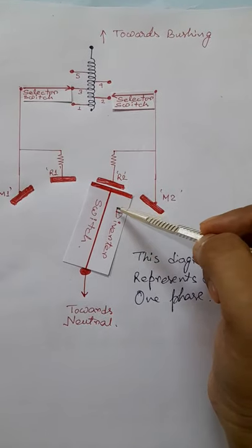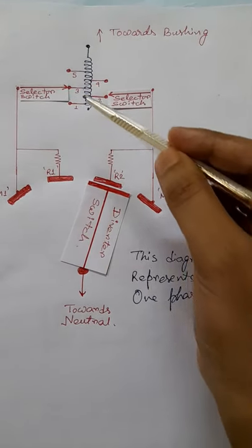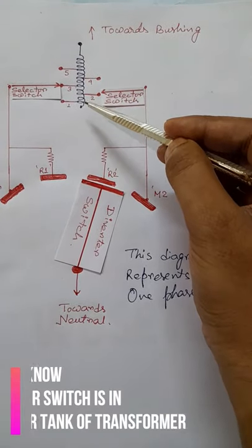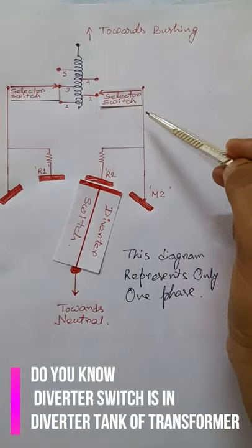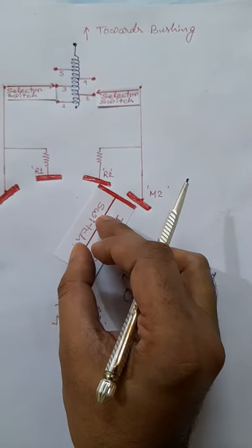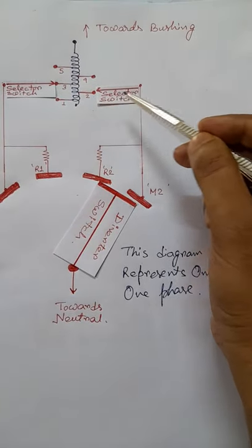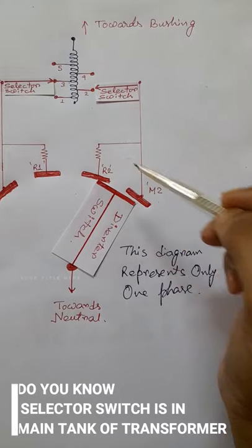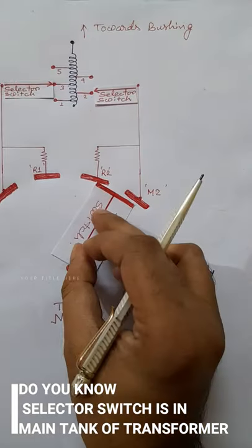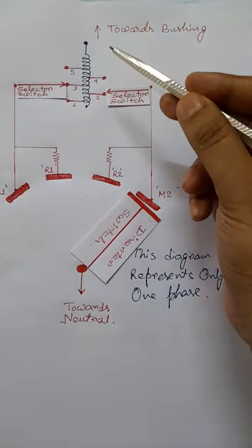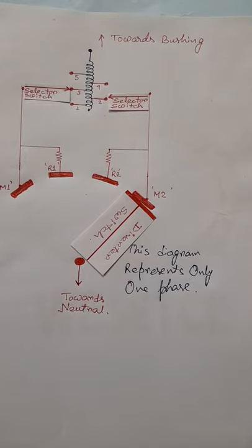The diverter switch keeps moving in the clockwise direction and at a point it is only connected with R2, so tap three is disconnected and total load current flows through tap two. Then it moves to a position where current flows through R2 and M2, and finally reaches the position where total load current is flowing through tap two.